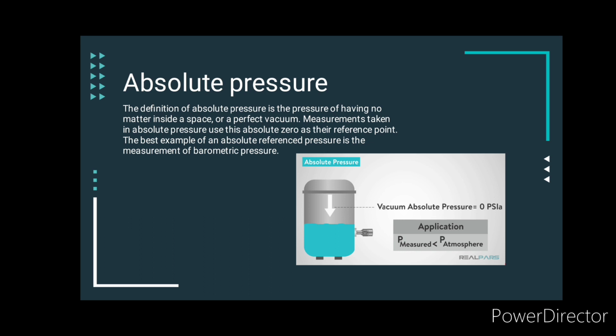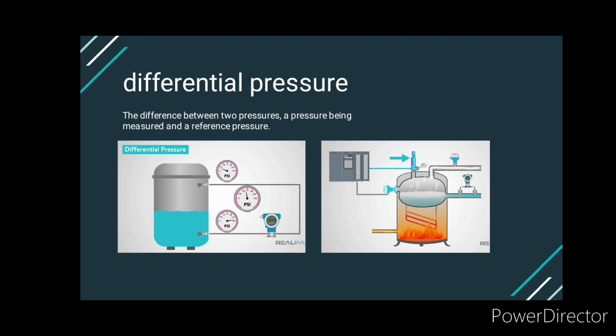So, absolute pressure. The definition of absolute pressure is the pressure of having no matter inside space, or a perfect vacuum. Measurements taken in absolute pressure use this absolute zero as the reference point. The best example of an absolute reference pressure is the measurement of barometric pressure. Differential pressure. The difference between two pressures, a pressure being measured and a reference pressure.